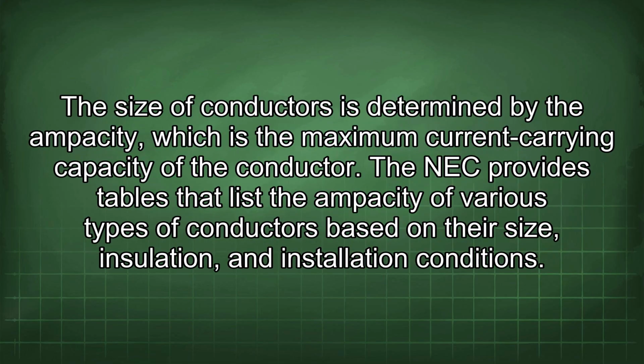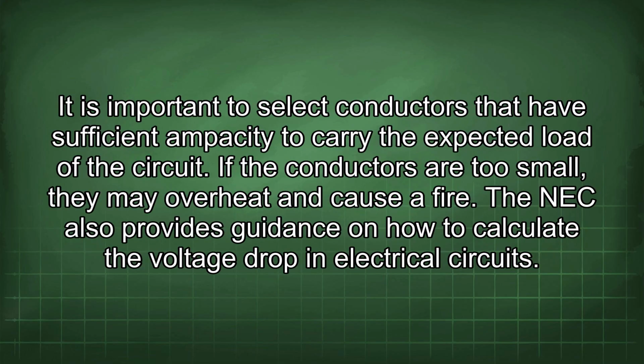The size of conductors is determined by the ampacity, which is the maximum current carrying capacity of the conductor. The NEC provides tables that list the ampacity of various types of conductors based on their size, insulation, and installation conditions. It is important to select conductors that have sufficient ampacity to carry the expected load of the circuit. If the conductors are too small, they may overheat and cause a fire.